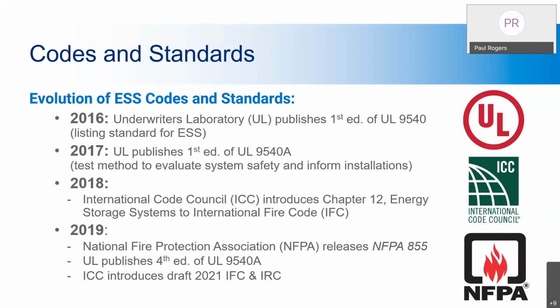The next thing that came about was destructive testing. Inside the code they have this thing called large-scale fire testing, but there was no criteria on what large-scale fire testing was, so they needed something uniform. UL put their heads together and came up with this thing called UL 9540A. The first edition was in 2017.